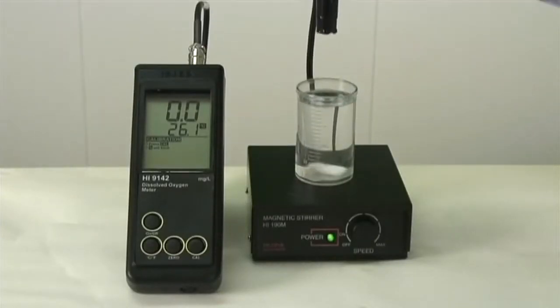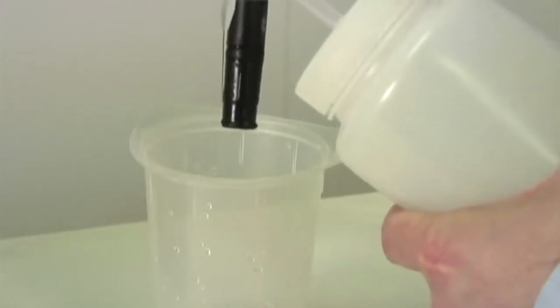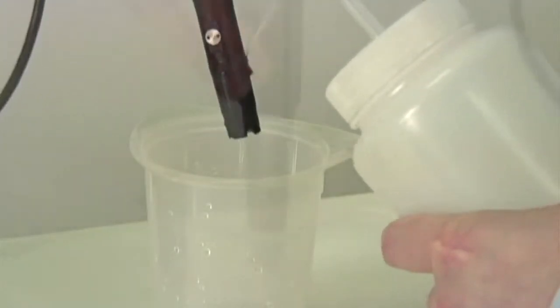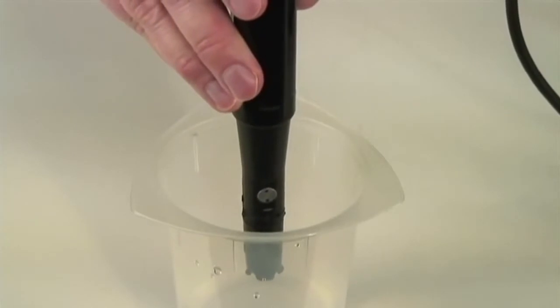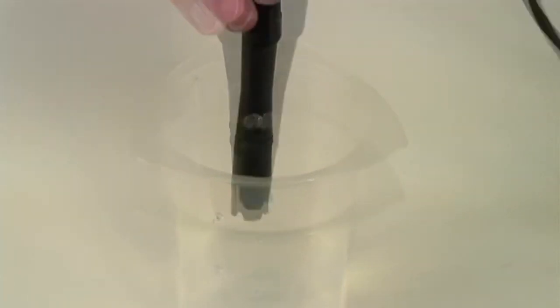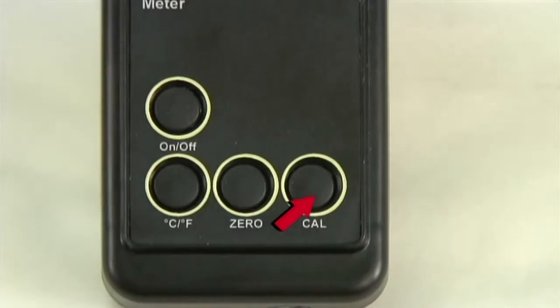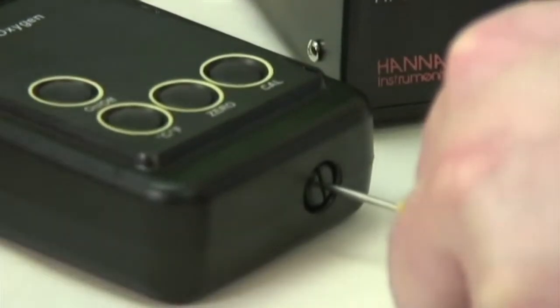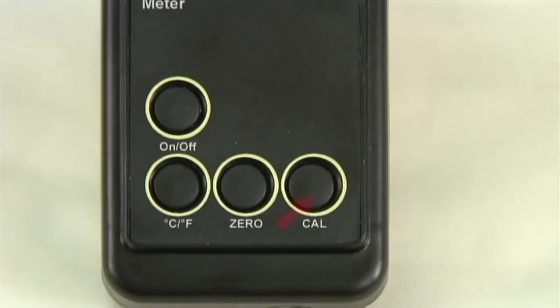Remove the probe from the zero oxygen solution and rinse it with DI water to remove any residual standard. Keep the probe facing downwards as normal. Tap it a little to remove any DI. Keeping the probe in air but holding it over water, press the Cal button. Adjust the slope trimmer on the bottom of the meter to 100%. Press Cal to confirm the 100% calibration. And now you're done. Be sure to put your protective cap back on if it'll be a while until you take a measurement.